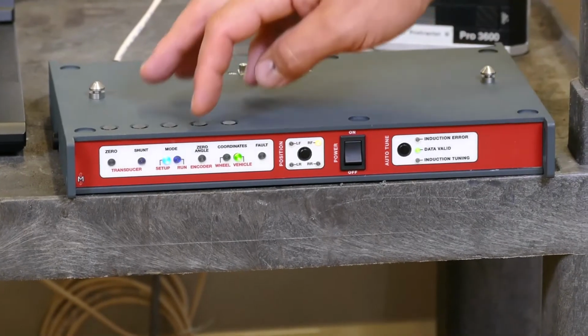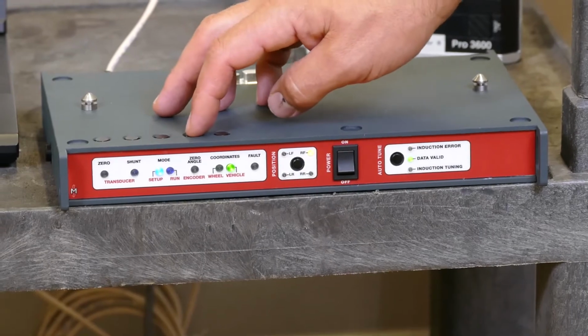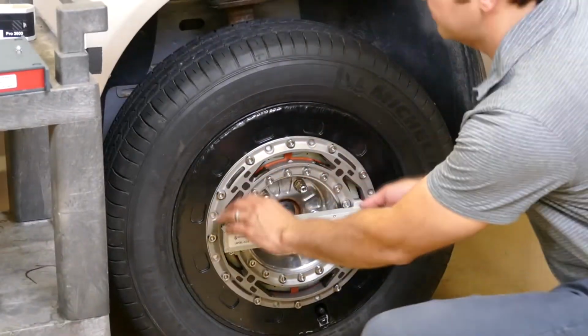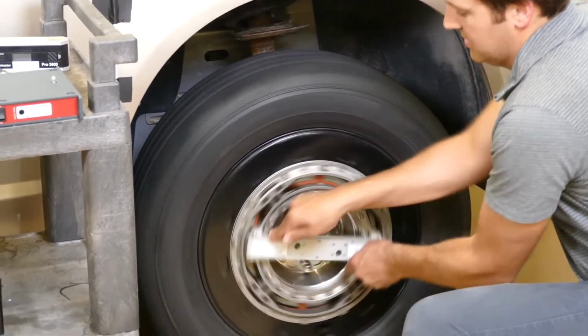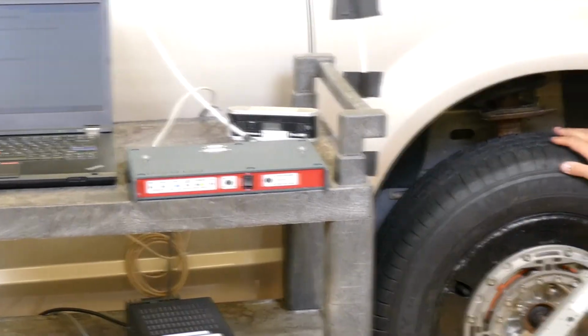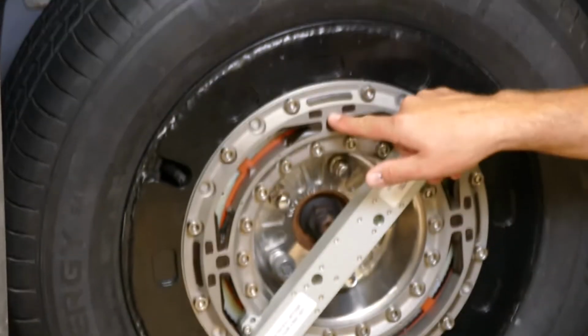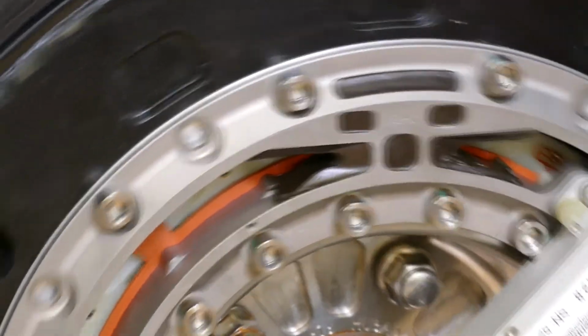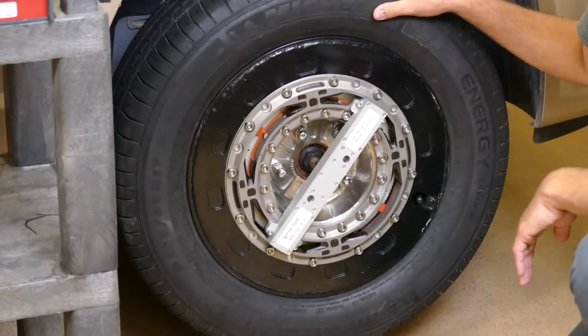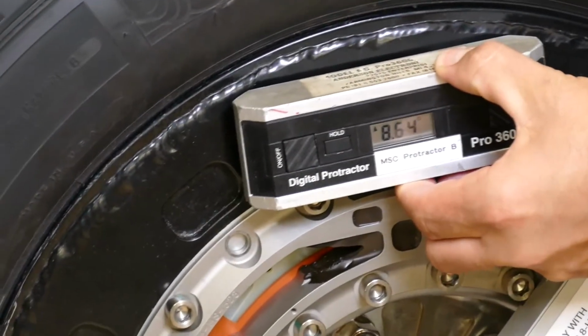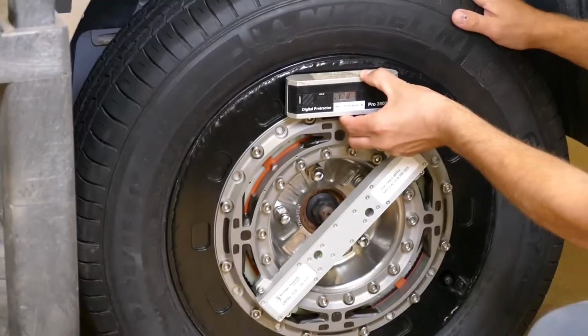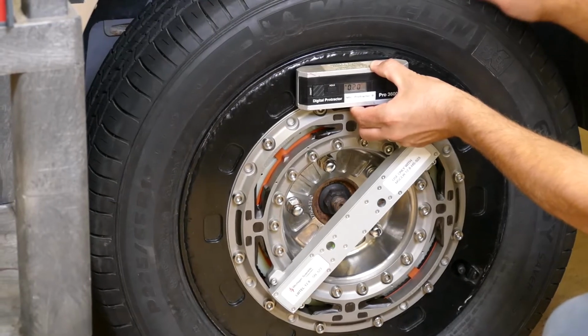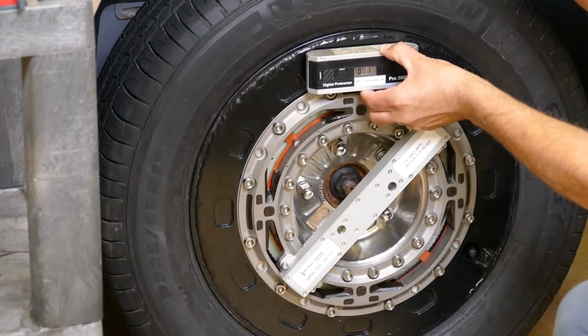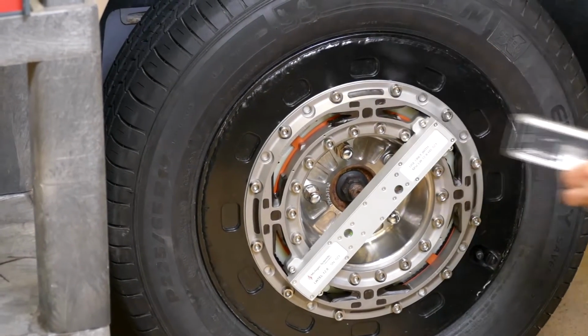The next step is to do the zero angle. For that, we're still in setup mode. We press the zero angle button, and we rotate the transducer until we see the light start to flash on the zero angle button. Once it starts to flash, then we find the Z plus arrow on the transducer. It's hard to see, but it's right there. So you want the Z plus arrow pointing vertically towards the ground. Point straight down. We're going to take a digital level, lay it across the top bolts, and rotate the wheel until we get within 0.2 or so of a degree. Once we have it pointing vertically towards the ground, we press the zero angle button again.